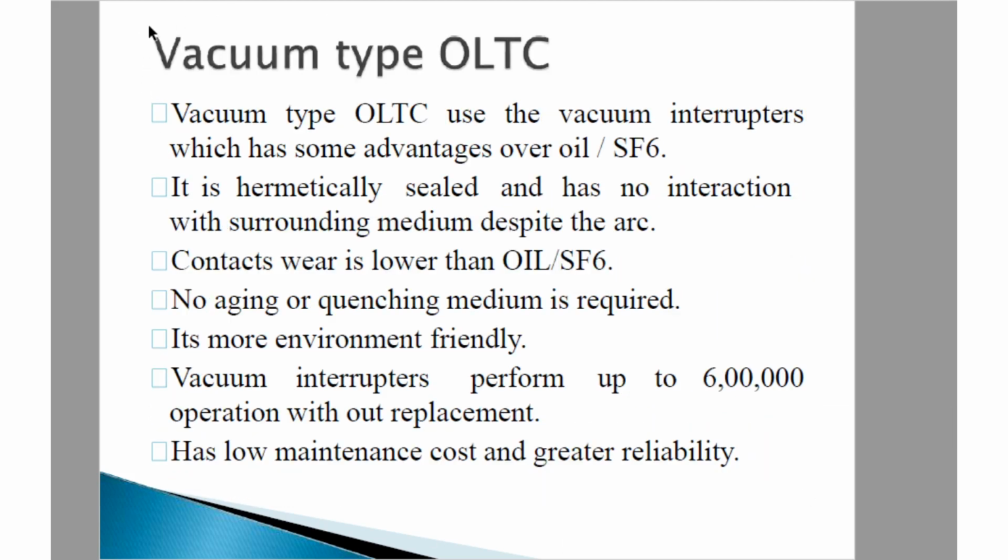Now there is a type called a vacuum type OLTC. So this is for the information. The vacuum type OLTC uses vacuum interrupters which have some advantages over oil and SF6. It is hermetically sealed and has no interaction with the surrounding medium despite the arc. The contact wear is lower than oil or SF6.